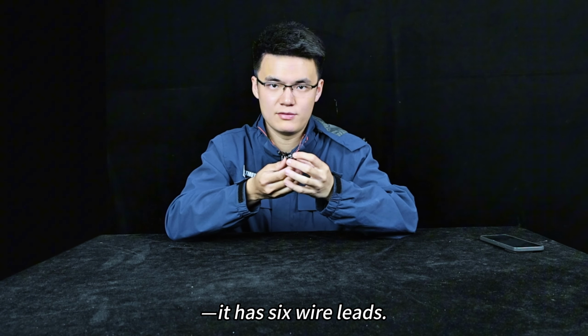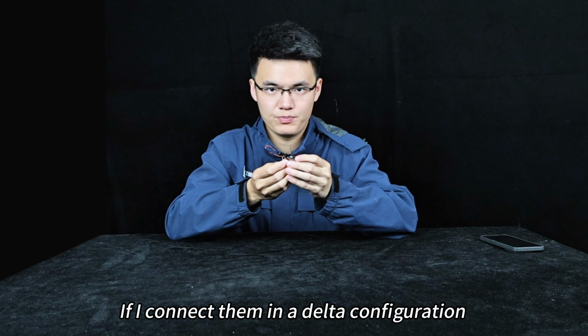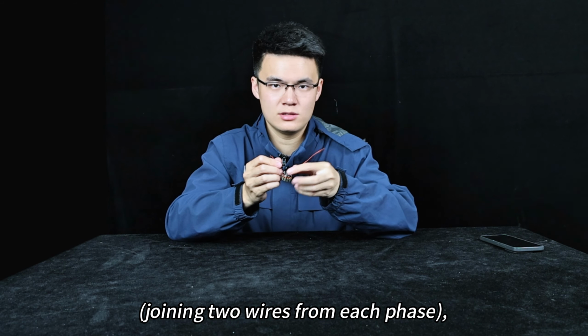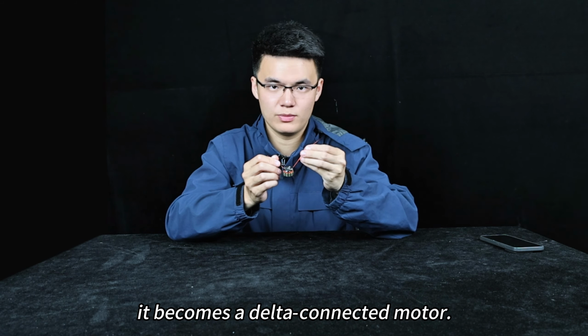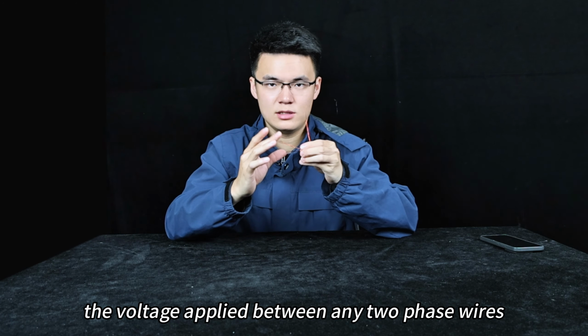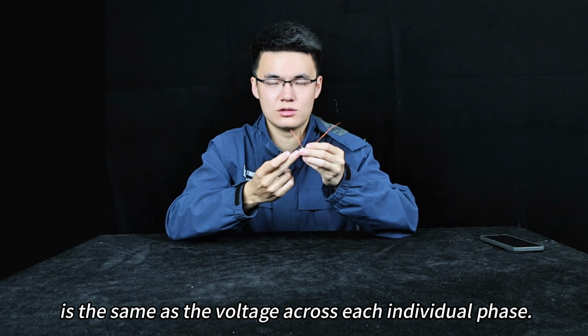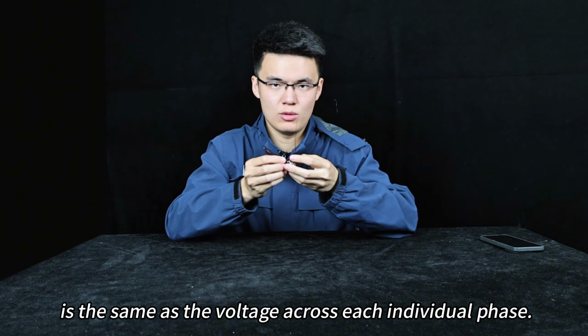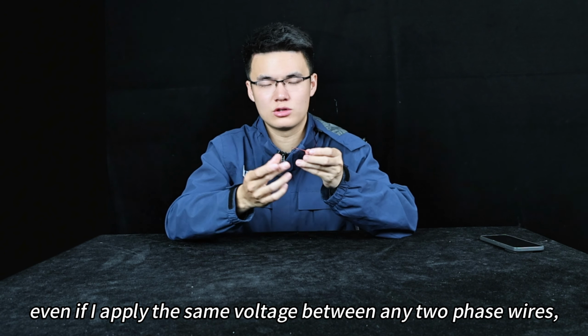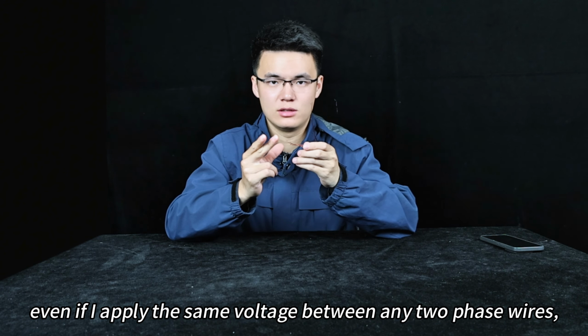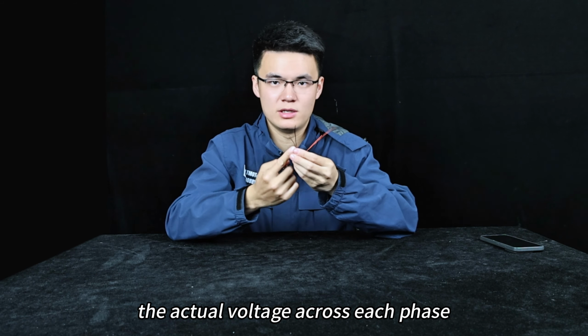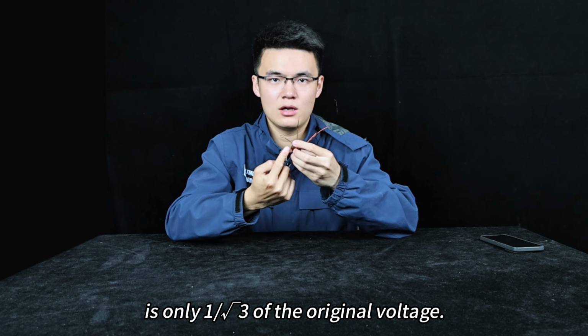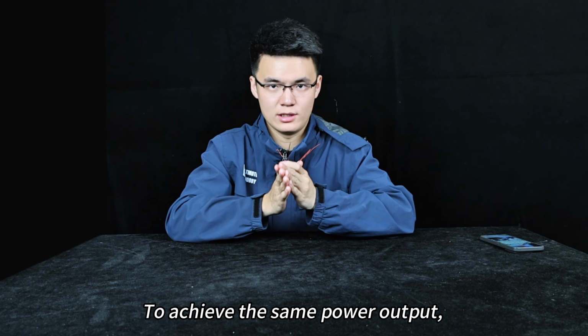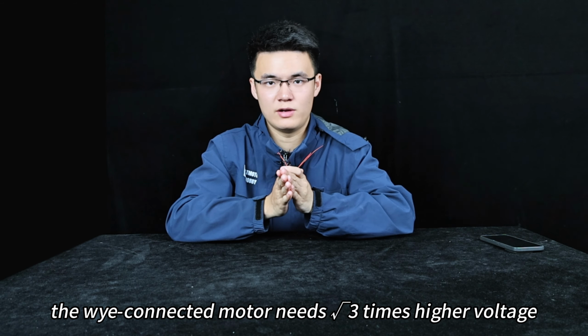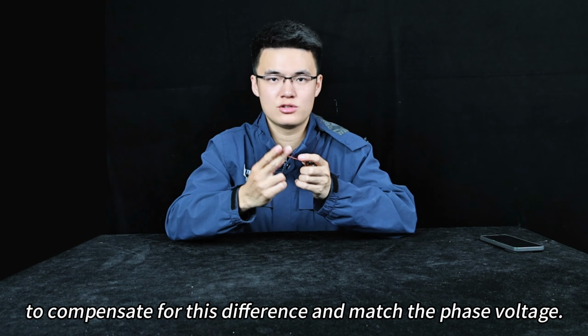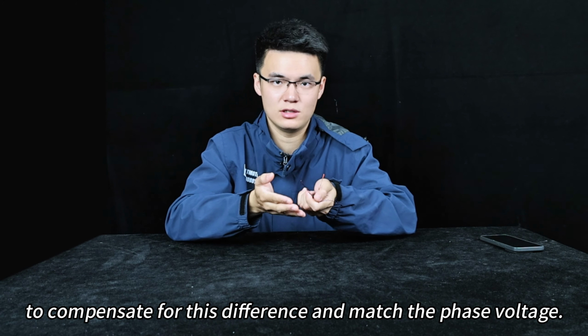It has 6 wire leads. If I connect them in a delta configuration, joining 2 wires from each phase, it becomes a delta-connected motor. In this case, the voltage applied between any 2 phase wires is the same as the voltage across each individual phase. But if I switch to a Y connection, even if I apply the same voltage between any 2 phase wires, the actual voltage across each phase is only 1/√3 of the original voltage. To achieve the same power output, the Y-connected motor needs square root 3 times higher voltage to compensate for this difference and match the phase voltage.